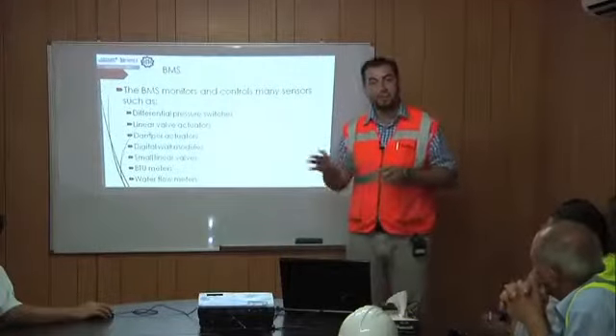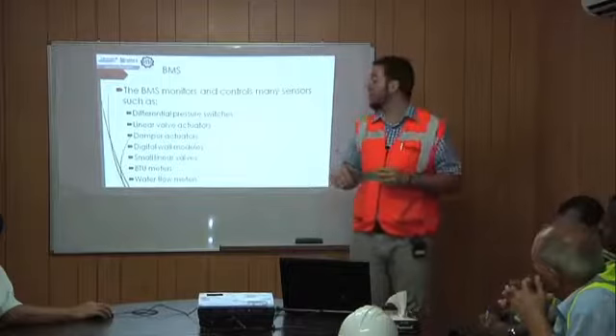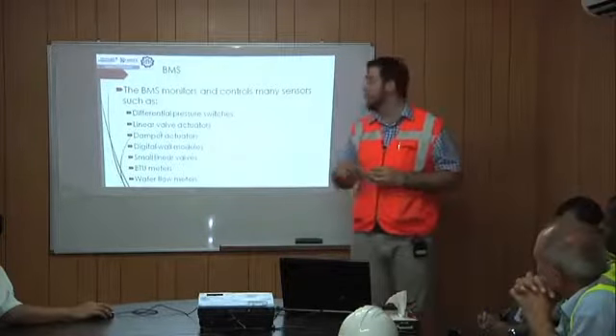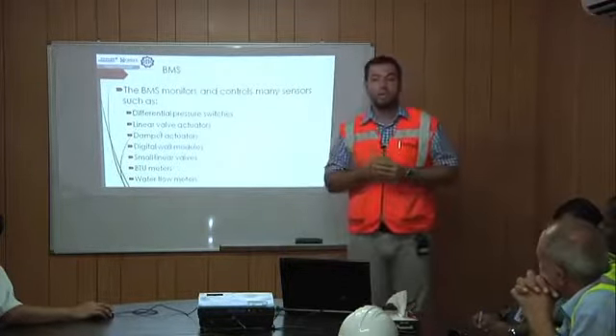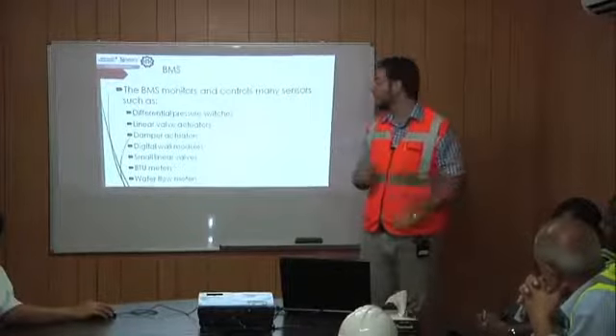Once you set up the temperature that you require, either through the thermostat or through your BMS, the linear actuators will actually adjust themselves to supply whatever required volume of chilled water to the RTU and to make it either colder or hotter based on the specific temperature.